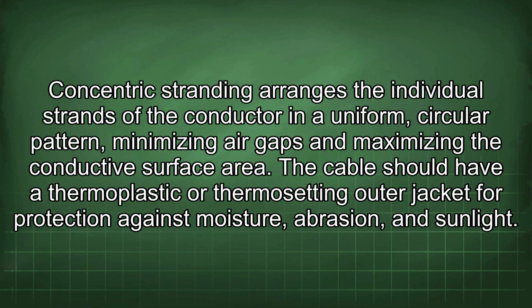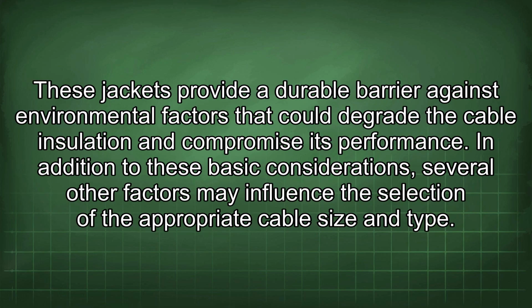Concentric stranding arranges the individual strands of the conductor in a uniform, circular pattern, minimizing air gaps and maximizing the conductive surface area. The cable should have a thermoplastic or thermosetting outer jacket for protection against moisture, abrasion, and sunlight. These jackets provide a durable barrier against environmental factors that could degrade the cable insulation and compromise its performance.